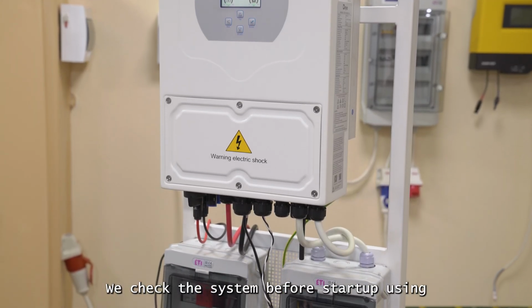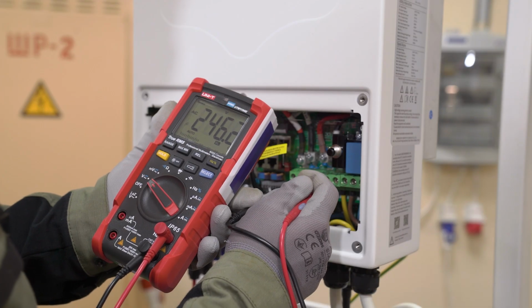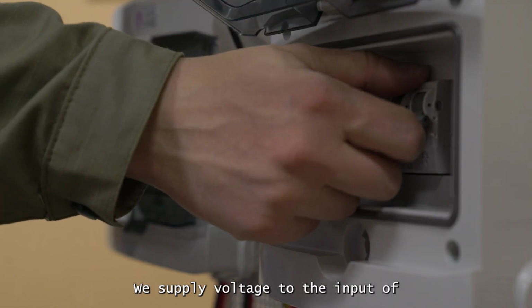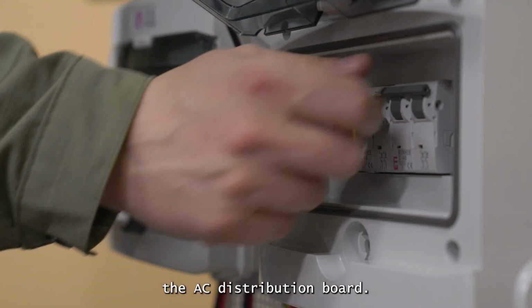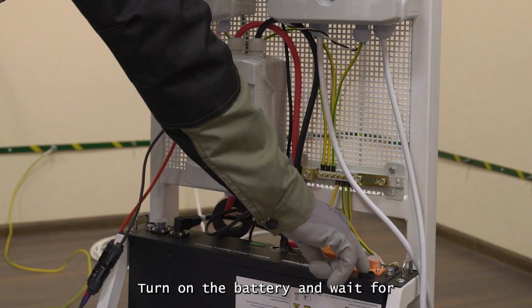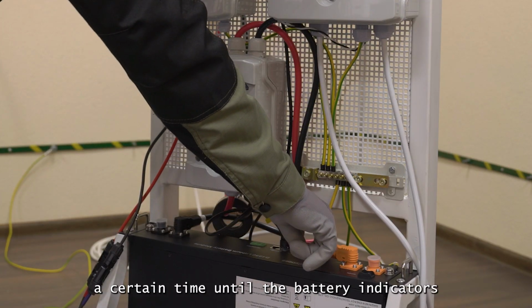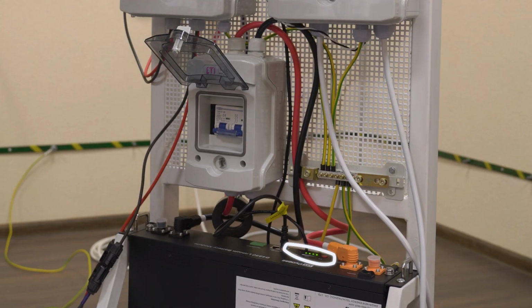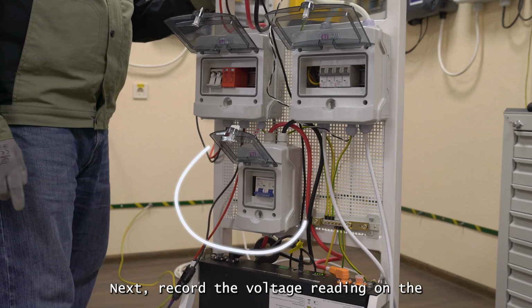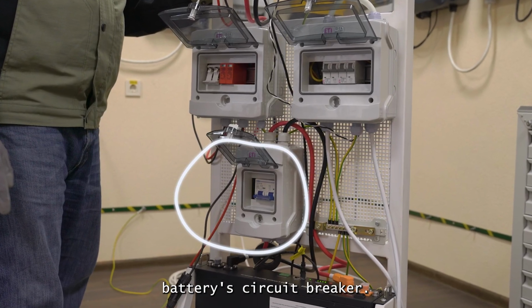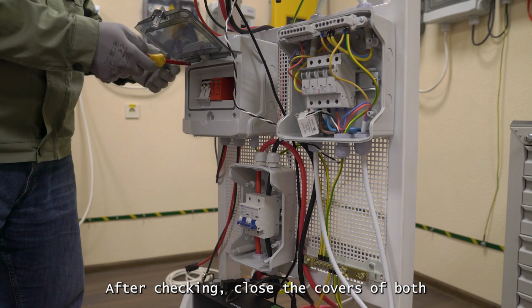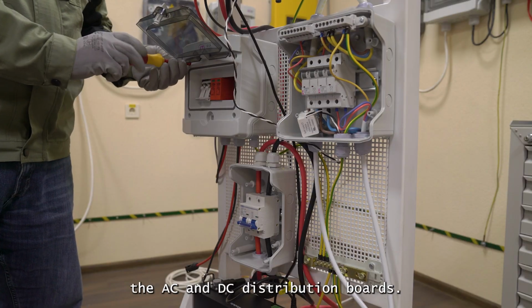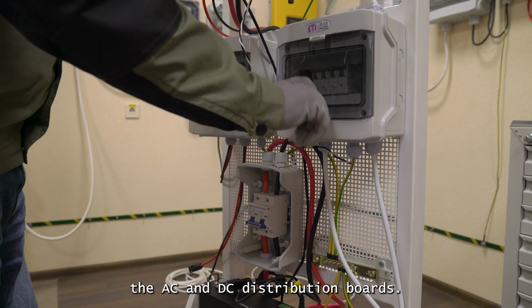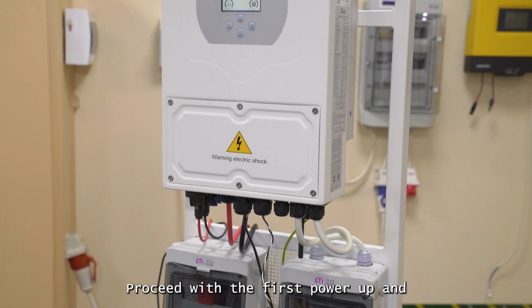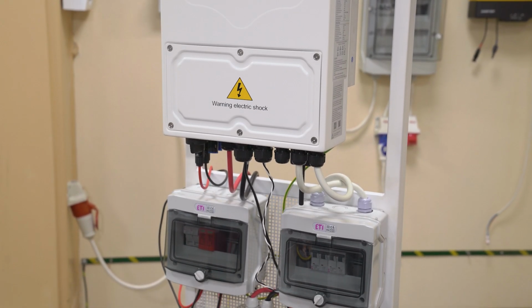We check the system before startup using a multimeter. We supply voltage to the input of the AC distribution board. Turn on the battery and wait for a certain time until the battery indicators light up. Next, record the voltage reading on the battery's circuit breaker. After checking, close the covers of both the AC and DC distribution boards. Proceed with the first power-up and configuration.